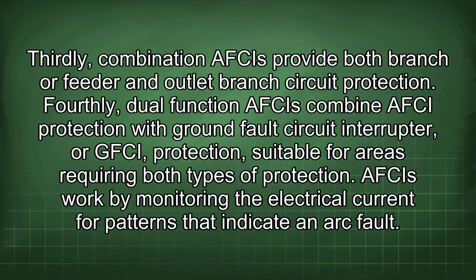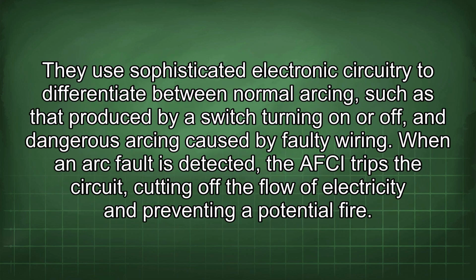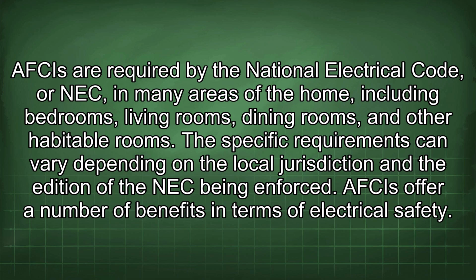AFCIs work by monitoring the electrical current for patterns that indicate an arc fault. They use sophisticated electronic circuitry to differentiate between normal arcing, such as that produced by a switch turning on or off, and dangerous arcing caused by faulty wiring. When an arc fault is detected, the AFCI trips the circuit, cutting off the flow of electricity and preventing a potential fire. AFCIs are required by the National Electrical Code, or NEC, in many areas of the home, including bedrooms, living rooms, dining rooms, and other habitable rooms. The specific requirements can vary depending on the local jurisdiction and the edition of the NEC being enforced.